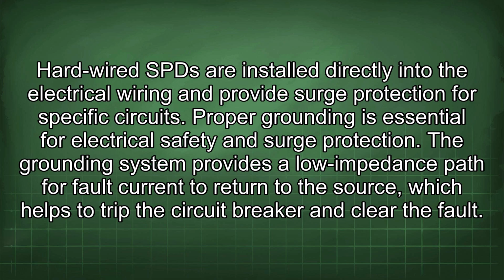Proper grounding is essential for electrical safety and surge protection. The grounding system provides a low impedance path for fault current to return to the source, which helps to trip the circuit breaker and clear the fault.